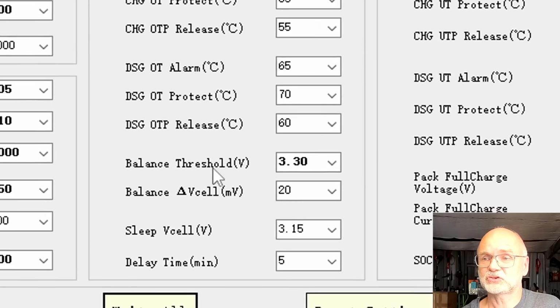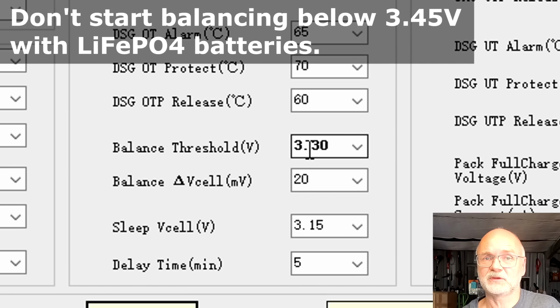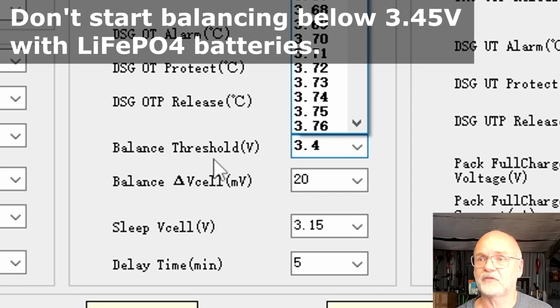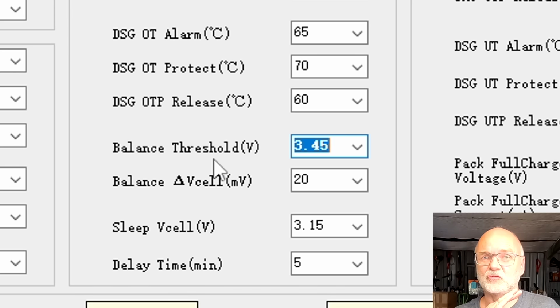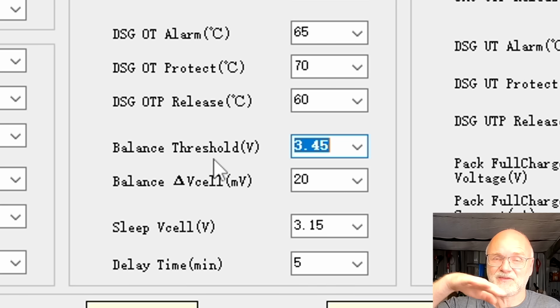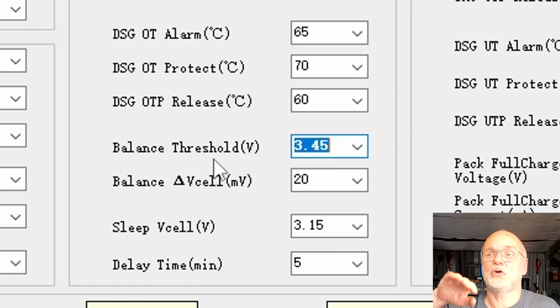The balance threshold start voltage with 3.3 volts is a bit too low for my taste. So I would set this one to 3.45 volts. Because there's no reason to start balancing before 3.45 volts. Even at 3.4 volt, it is still a bit low. And if you charge this battery with a high current, you can easily reach 3.4 volts already, charging voltage. And then the balancer would start balancing, even though there is nothing to balance. So you really want to get out of this knee, of this elbow, into the steep part of this curve, and then start balancing, not before that.